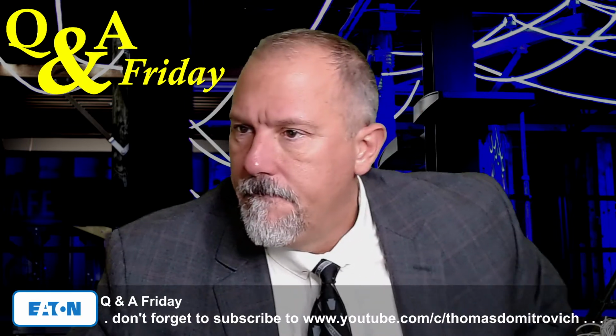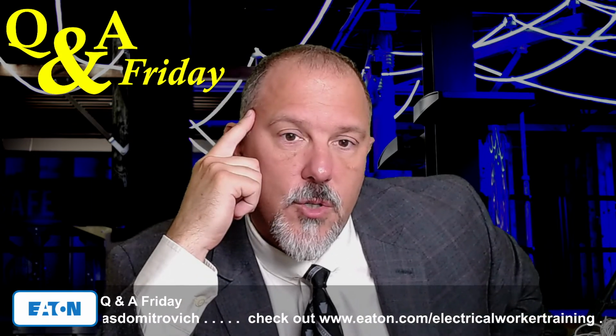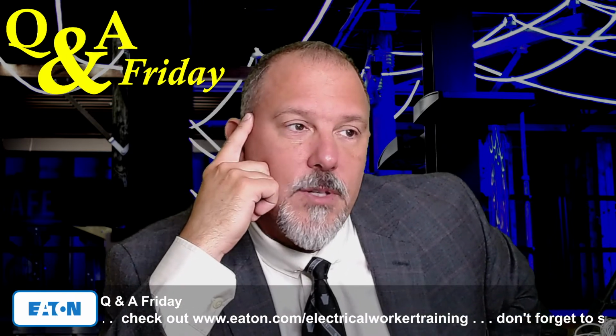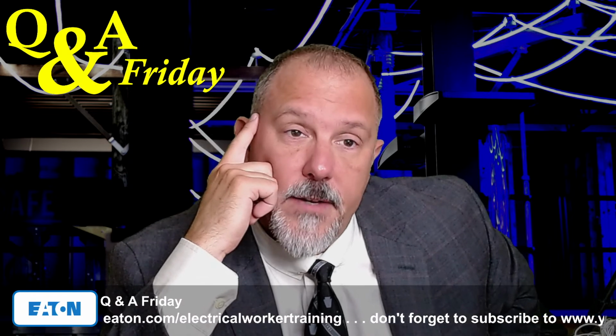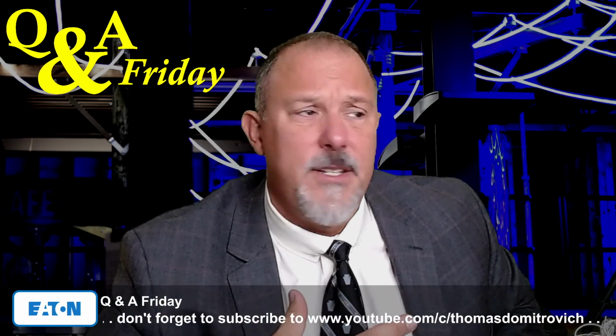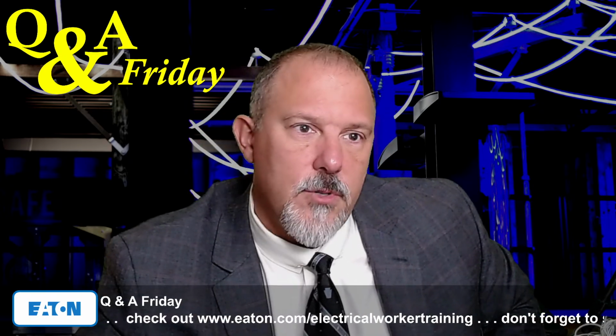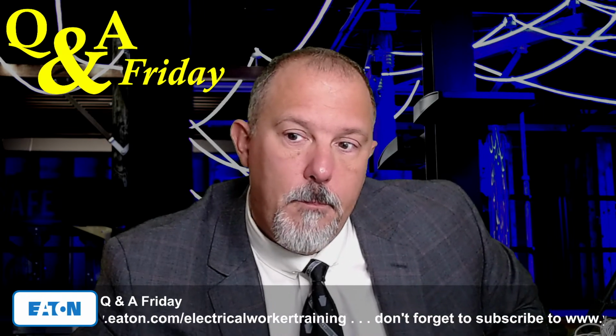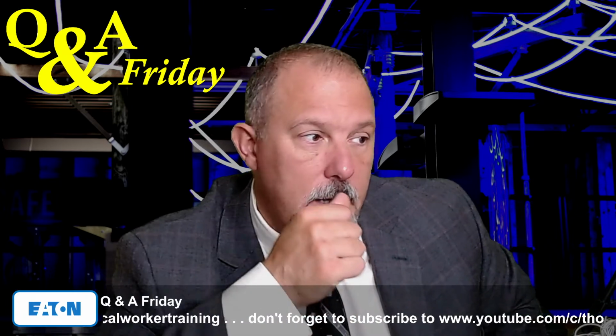Okay, there was another question in there. Let me find it. So that answers that question about damaged equipment. And smoke and fire damaged equipment is a challenge. I was once on an inspection with an electrical inspector, and we went to a fire damaged home. And he was very point blank with me. He said, okay, Tom, we walked into the living room, and the paint's peeled off the wall, but there wasn't any fire in there. There was smoke damage. It was very difficult, I had to have a rag over my mouth because of the odor of fire and smoke. But we looked at lighting fixtures, and we looked at light switches and receptacles that had visible damage from heat. But do you need to replace it? And there wasn't a good reference out there.